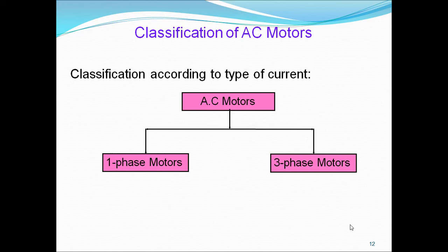If you go for a star connection, it has another wire also, four wires. The additional one is called neutral. It has three phases and one neutral. The supply between the lines, that is R, Y, B, is 440 volts. And the supply between phase and neutral is 230 volts.